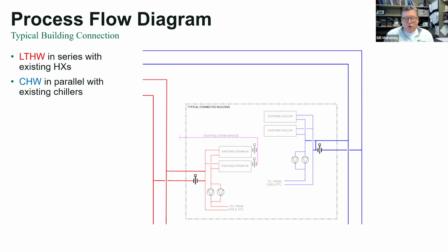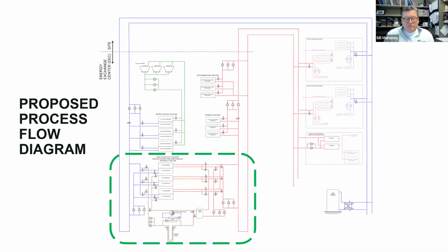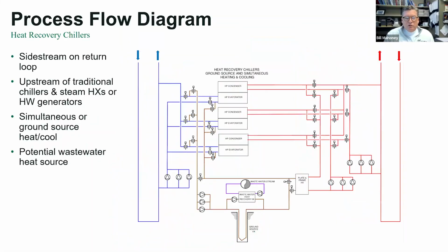Next slide jumps out the whole area. And if we jump over and focus on the plant, it has 2 parts. So this is the initial part of the plant. The hot water comes back at 110 here from the site. And the first thing we have it do is it hits our heat recovery chillers. That's these guys here, evaporators and condensers. So the hot side goes out from the condenser, and the cold side comes from the evaporator.